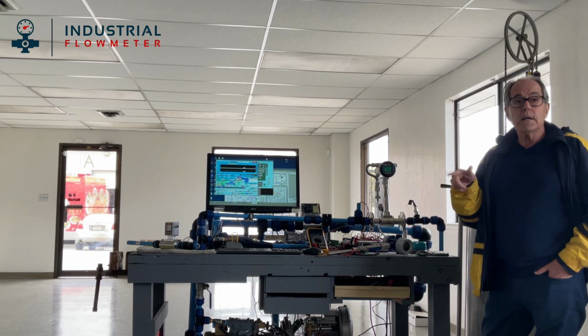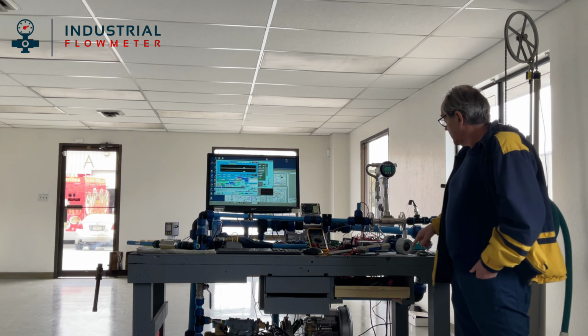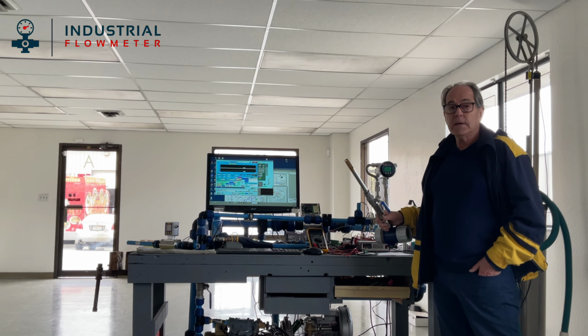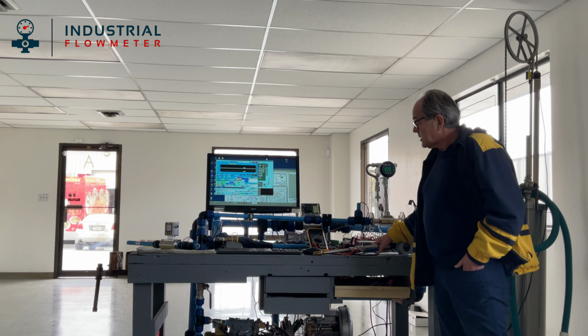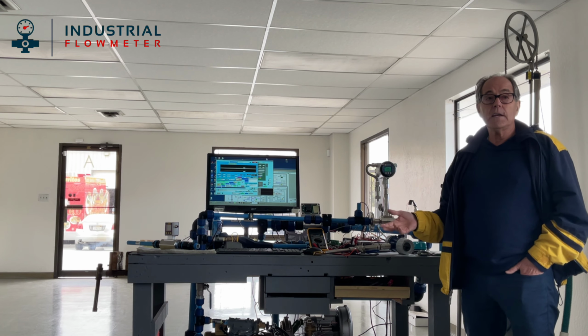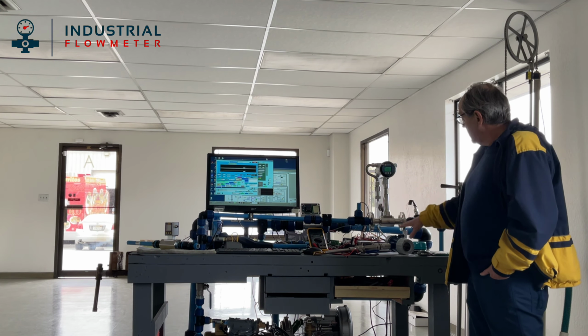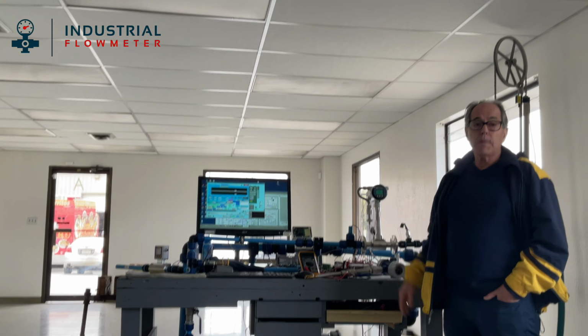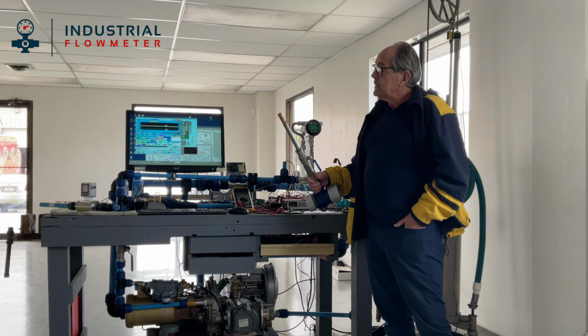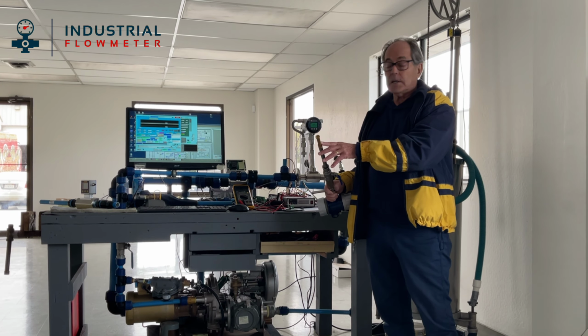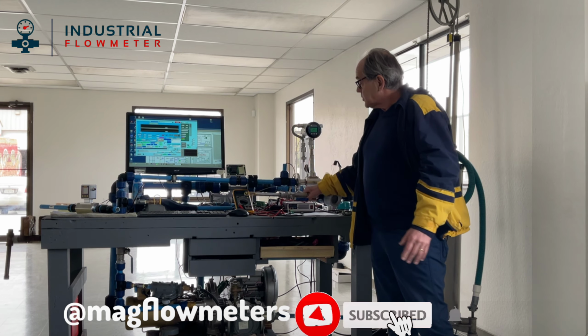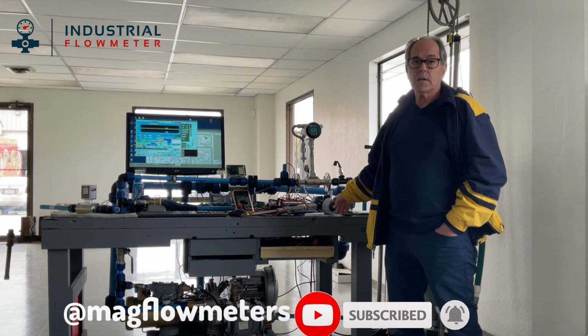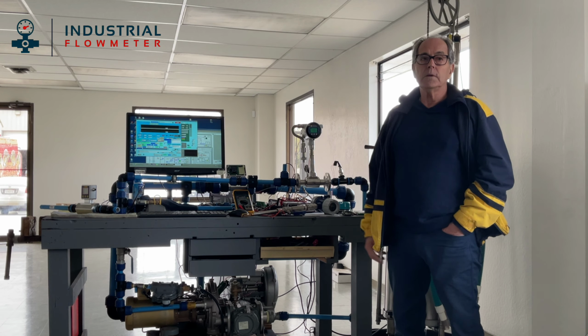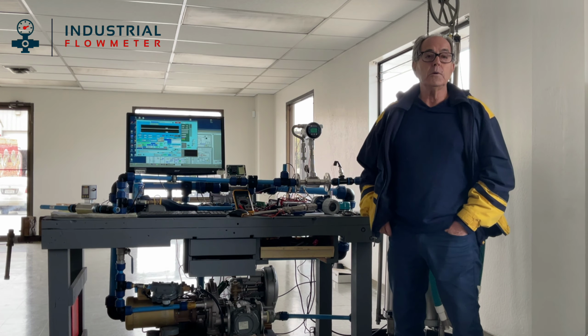We have to clean it up to turn it into a pretty square wave. And this one isn't a pretty analog signal. It has all kinds of sensitivities to all kinds of things that we do transfer functions on inside the micro. So this one's a little more complex, where we have to make transformations inside the electronics to indicate the flow in the customer's units that they want.